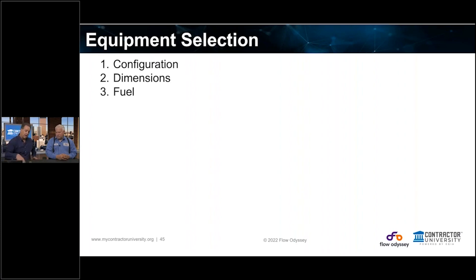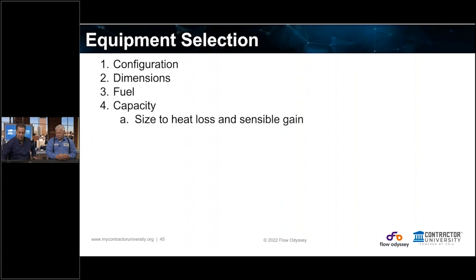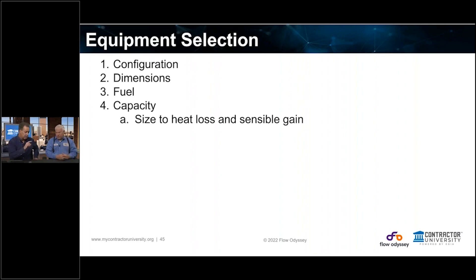The fuel — what fuel type do you have? Is it oil, gas, propane, or electric? The capacity — we know what the load is, so what is the capacity? On the heating side, we size to the heat loss. The calculation gives you both a heat loss and a heat gain. On the heat loss side, we pick equipment that gives us the output based on the load. If it's an 80% furnace, you have to upsize the furnace a little bit.